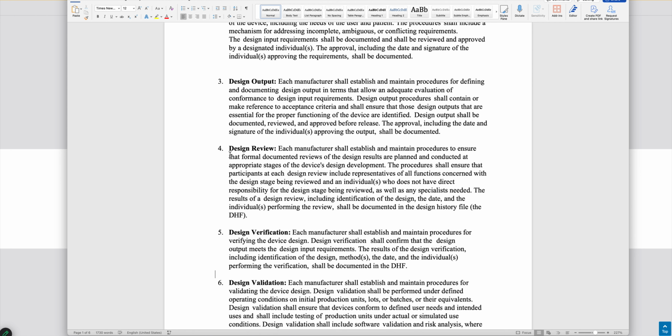Once we have established the design input, so what goes into the medical device, and the output, so what is getting out of that system or device, and after having reviewed and documented the fact that we checked the inputs and outputs and the processing in the device based on the patient and the team requirements, we will then document it, and then look into the verification of the design.